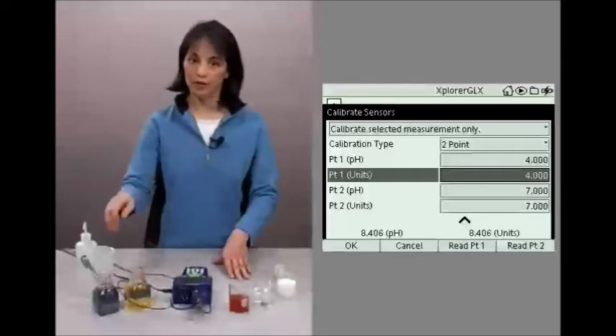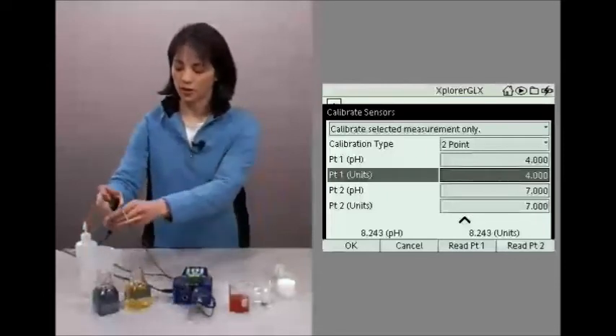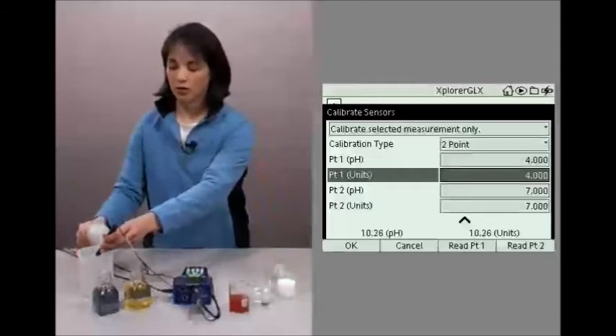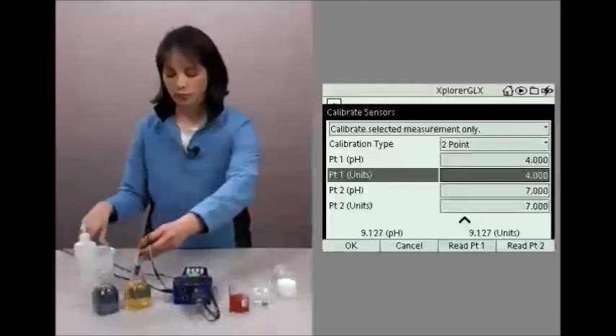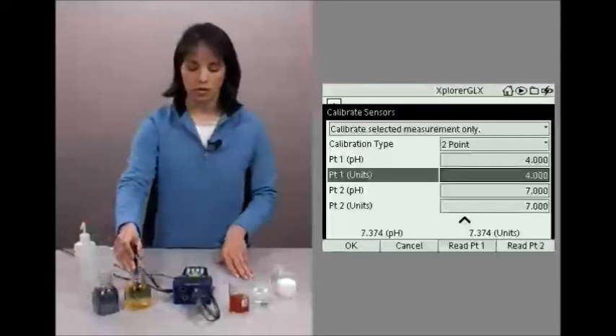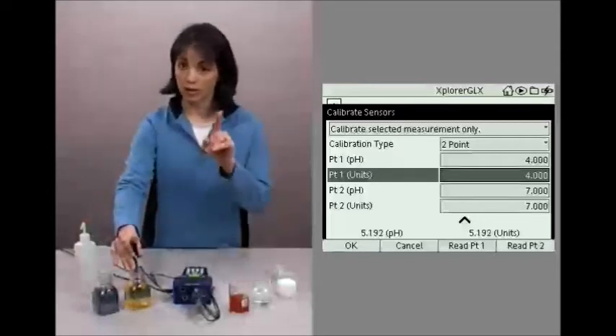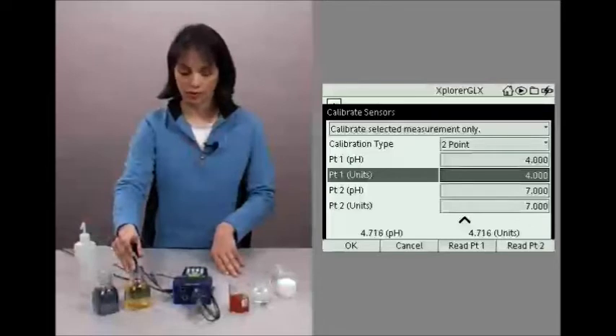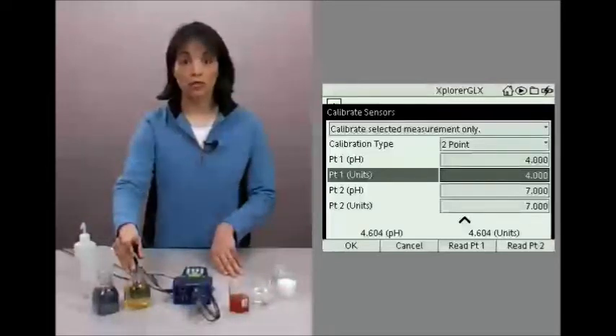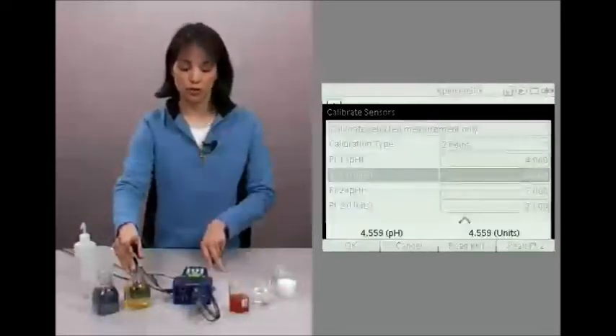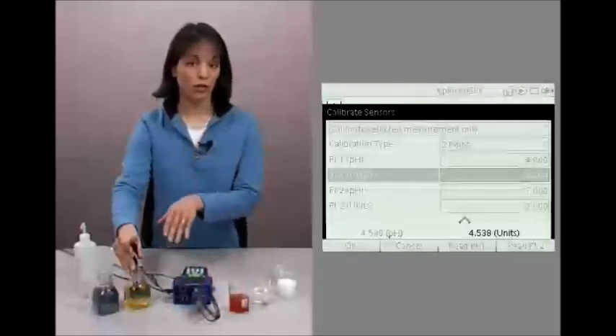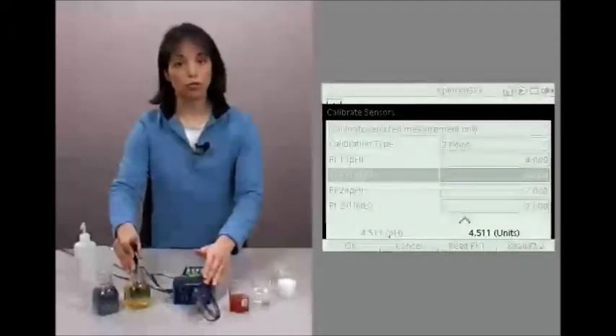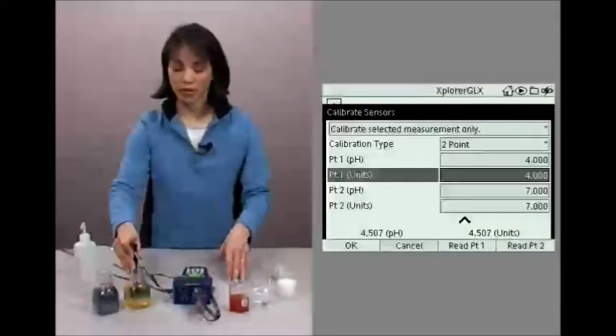Okay, now let's stick this into our, let me rinse it off, into our buffer solution. Okay, it's actually quite easy, and it's not that value 4 that you see in there currently. Take a look near the bottom of the screen. There are 2 live readings there. The one on the right, labeled units, is the raw value that the Xplorer GLX sees from the sensor. That is the value that we want to put in that second field, also labeled units.